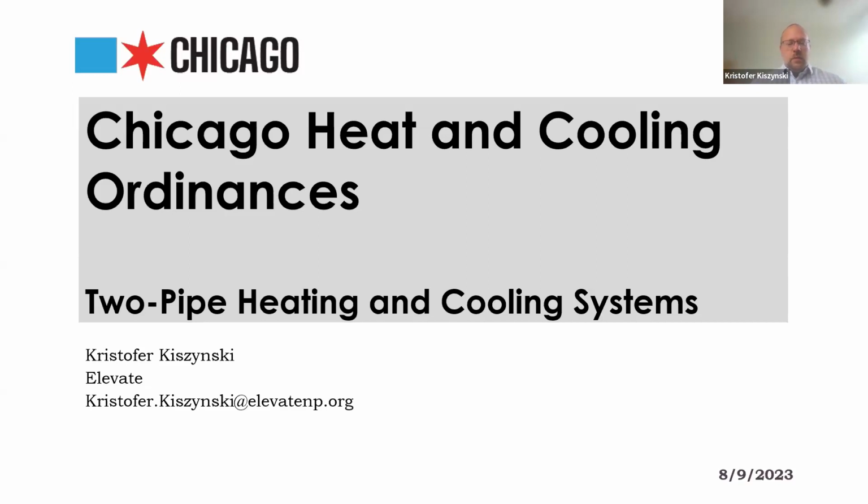But in these systems, only one or the other can occur, and the reason why we're talking about this today is because the cooling ordinance and the heating ordinance both apply in some of the transition months between the heating season and cooling season, and the cooling season and heating season. So the question becomes, how can we try to switch back and forth between these modes if we have a 2-pipe system?